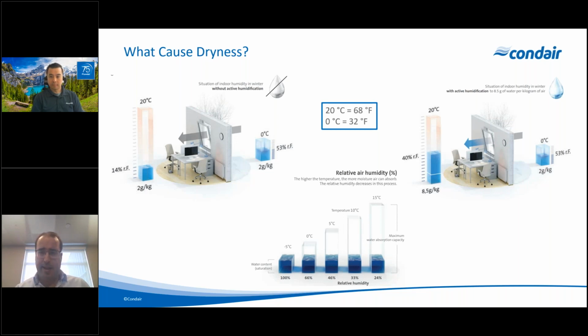On the right side, with active humidification, you bring in outside air, heat the air, but also add more absolute humidity to the air. So you're actually increasing your absolute humidity content, and your relative humidity also goes up.